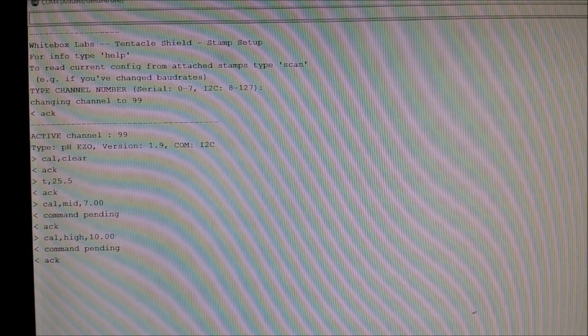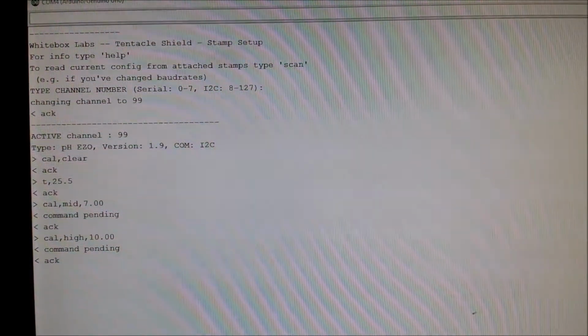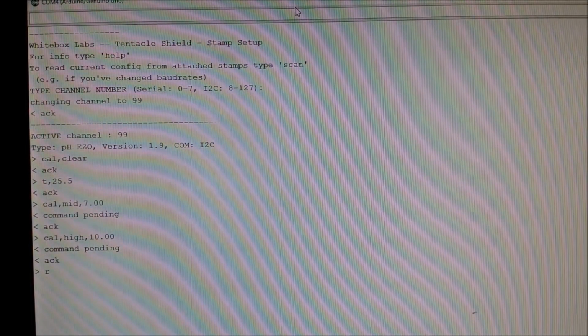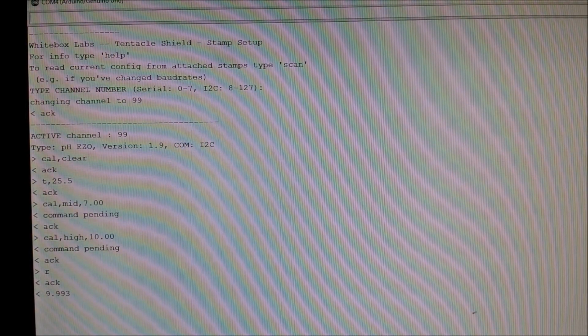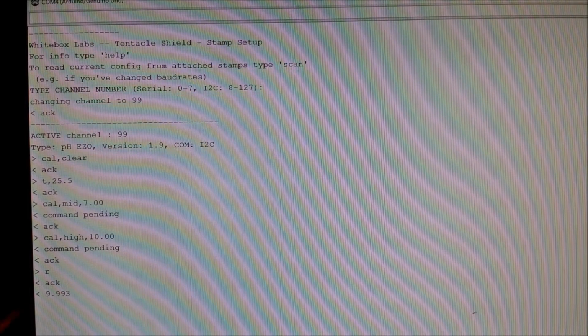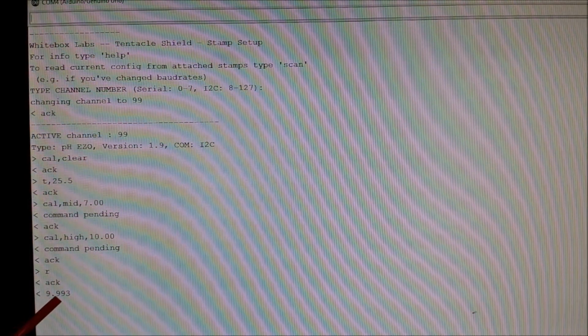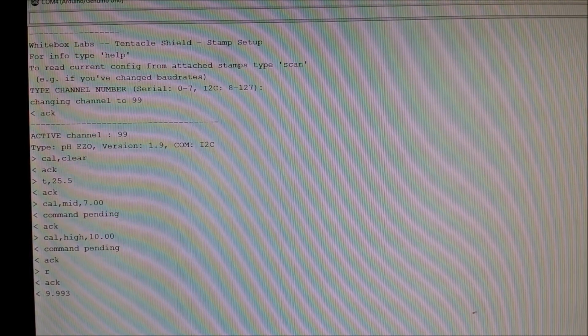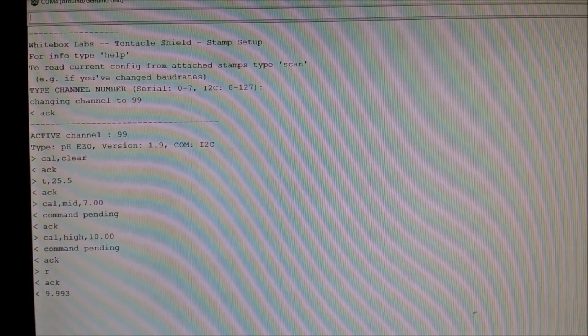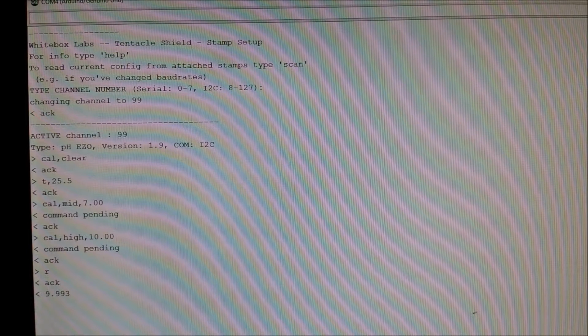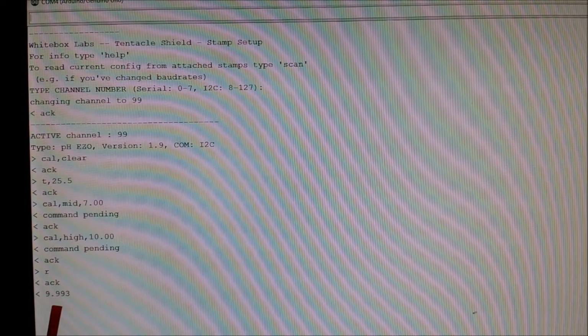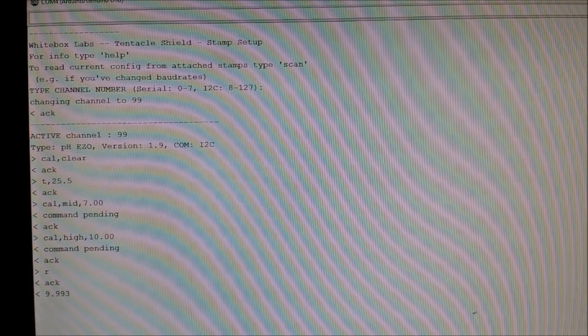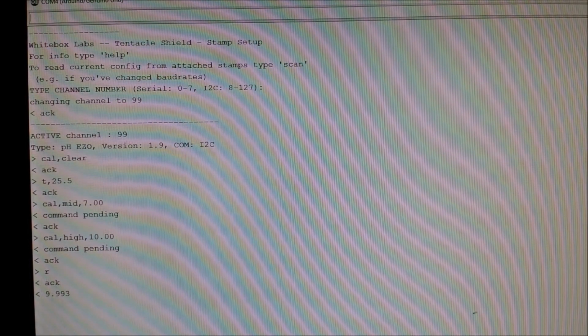Okay, so in the datasheet it talks about quick codes, and if you send it an R, it just takes a single reading. So I'm just going to type R, and then hit enter. And then you can see that it gives me an acknowledgement, and then it's telling me a pH of 9.993. Now, it's still in the pH 10 solution, so that's pretty accurate for my purposes. The difference, in my opinion, is probably going to be the temperature change. My solution probably isn't exactly 25.5, so that's where you're getting the least significant digit off.